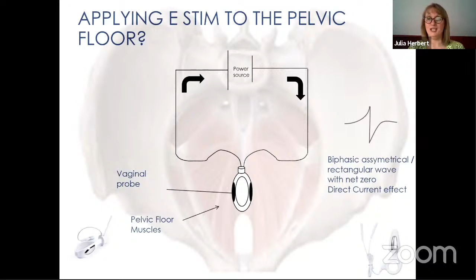Because we're not using a normal electrical circuit, if I want to plug my laptop in to charge it up, I have metal pins on my plug and I connect into the system in the house that has the mains electricity by putting metal against metal, which is a really good conductor. And the challenge that we have with patients is that we get this thing called impedance, and tissue impedance is a particular challenge. If we put a probe in the vagina or in the anus, we're against the mucosal membrane and we haven't got a metal pin plugging them in. So we need quite a lot of moisture there, as anything water-based is a good transmitter of the electrical energy. So tissue impedance, which is measured in ohms based on Ohm's law, can actually affect how much stimulation we can get into those tissues and whether we can get it to a therapeutic level.